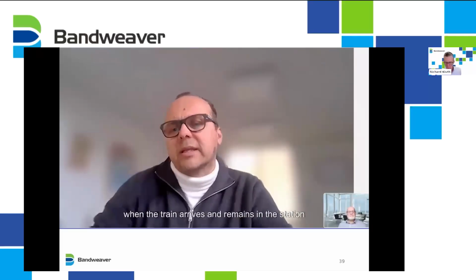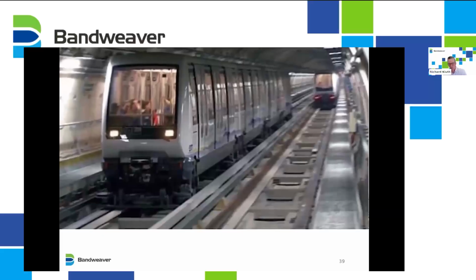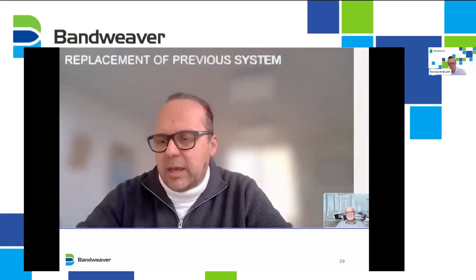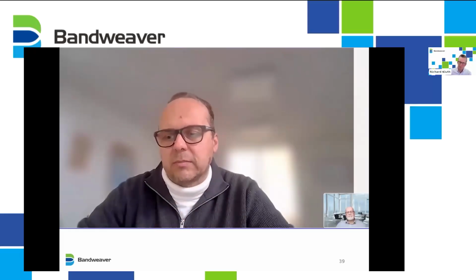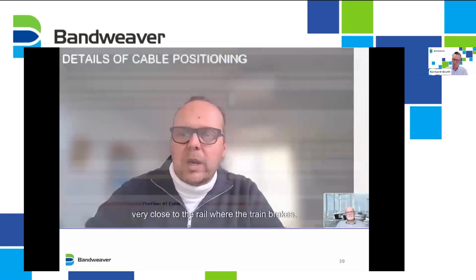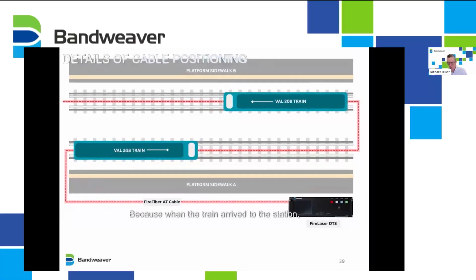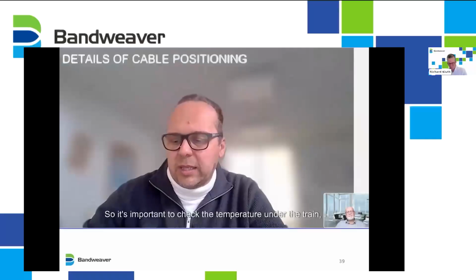Our customer has asked to find a solution to prevent fire and check the most important things is check the rate of rise when the train arrive and stay in the station, because we are driverless, nobody can check what's happening on the train about the fire. But they had an old system in this station, in all stations, and we are increasing the safety with a new system from Bandweaver. Another technology, no, because the request is to check the temperature very close to the rail where the train has the brake, because when the train arrives at the station, the brake has heavy work. So it's important to check the temperature under the train, very close to the wheel and very close to the brake.